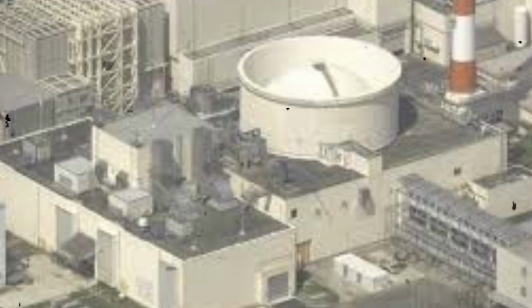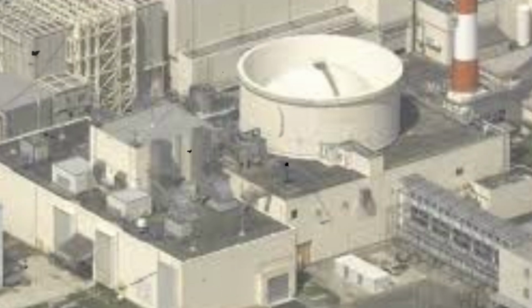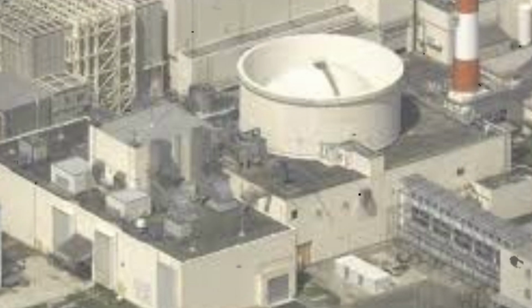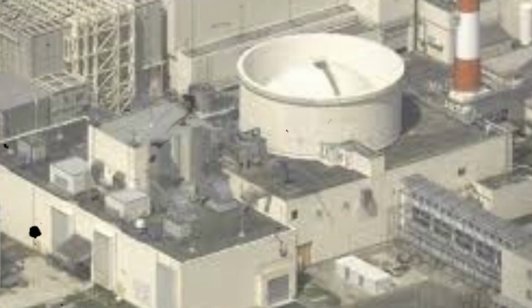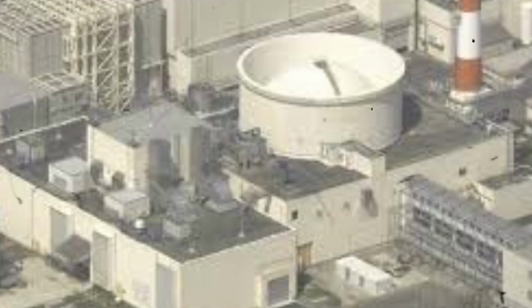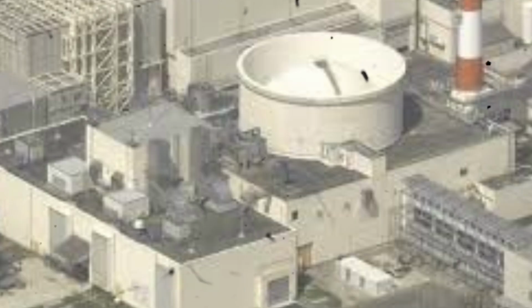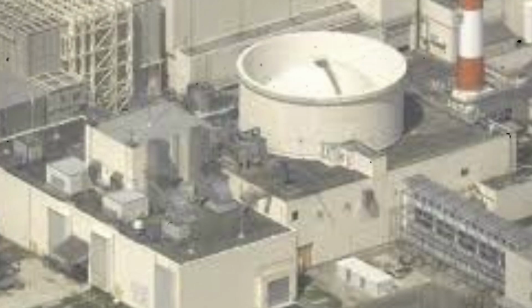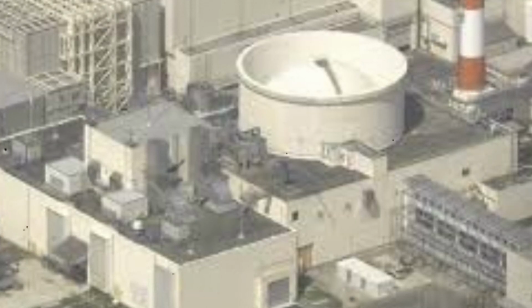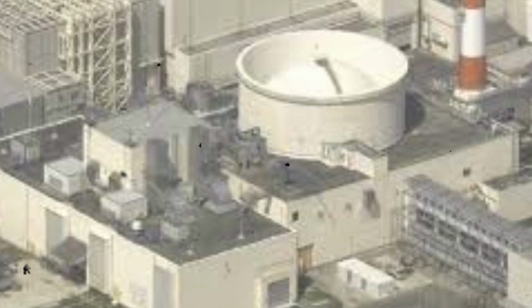Temperature measurement accuracy was unaffected because the thermocouple itself remained intact within the protective well. Flow rate measurements showed no variation because the crack opening was initially too small to affect bulk coolant flow. Pressure measurements remained normal because the crack did not initially penetrate completely through the well wall.